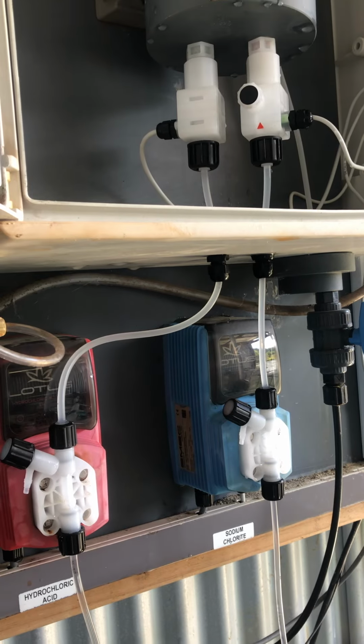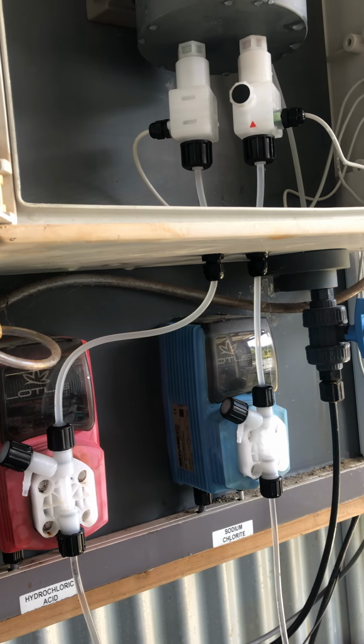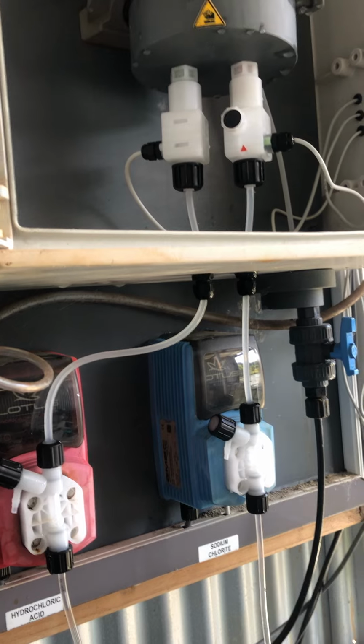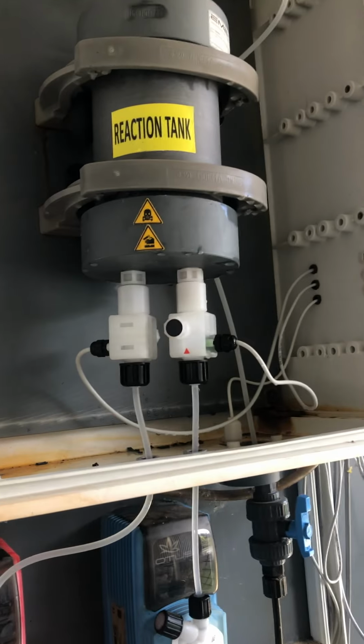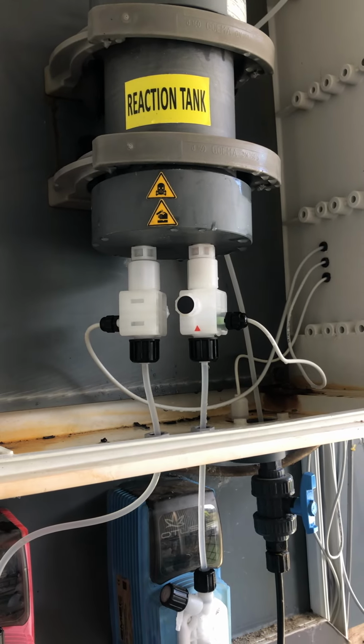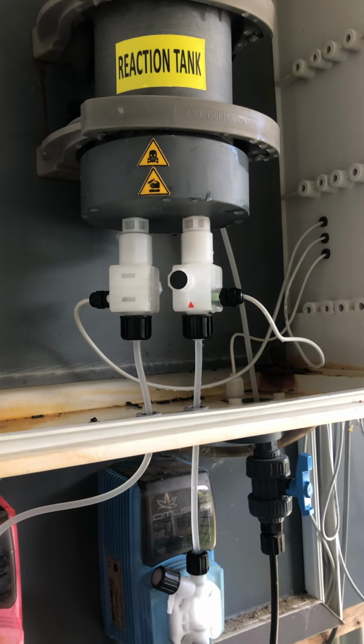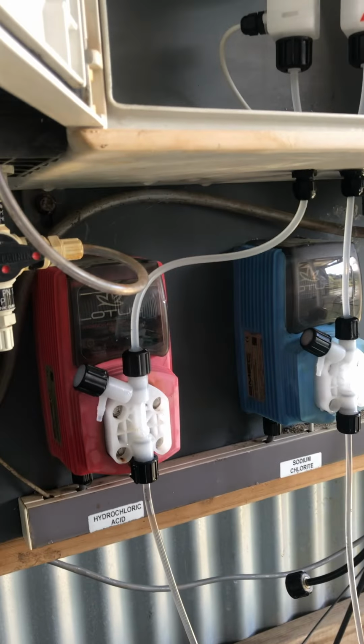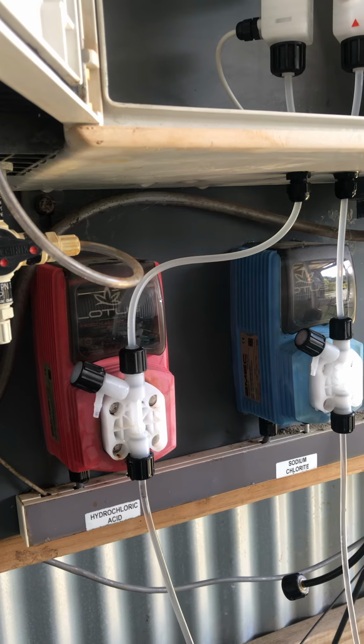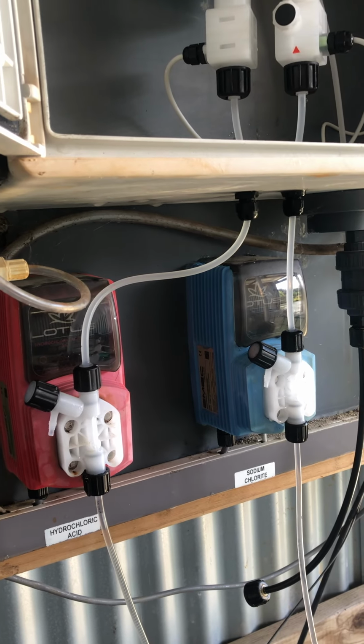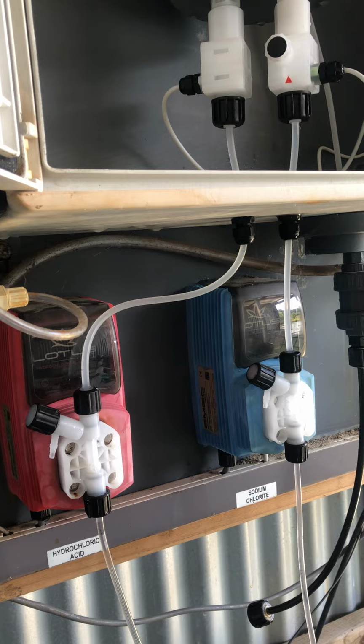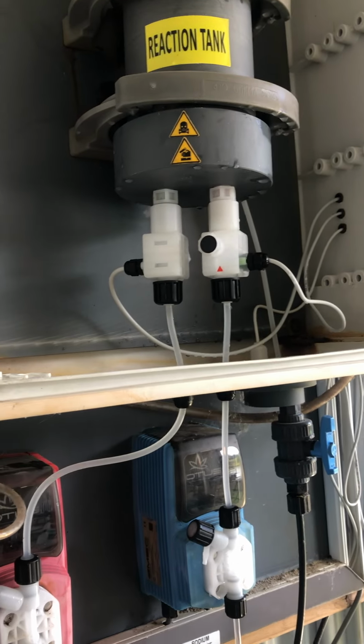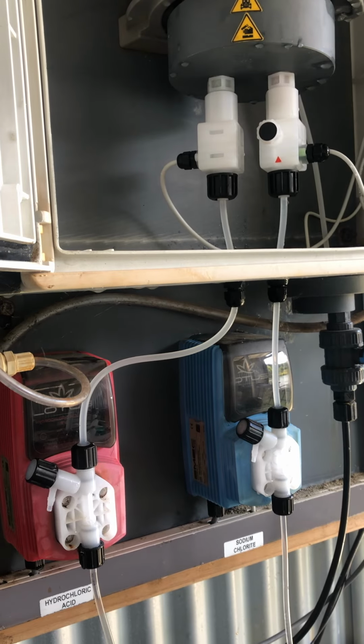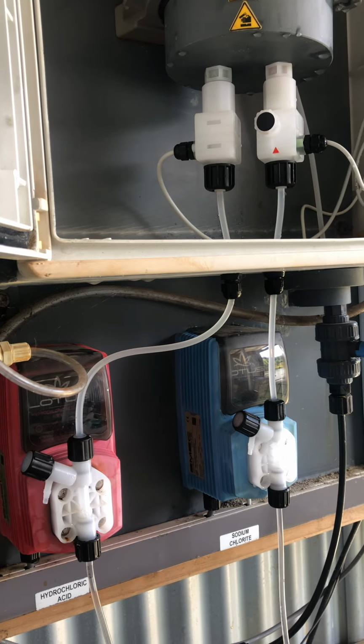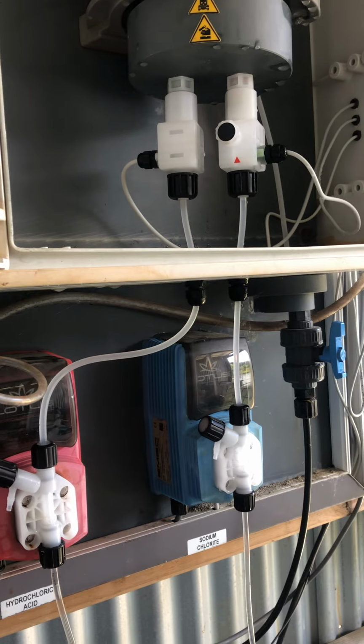We then replace the PVDF tubing. I recommend that you don't cut that initially. Disconnect it from the half-inch fittings in the bottom of the flow monitors and disconnect the 3/8 fitting on the top of the valve. Remove the tubing connectors where you can, then slide the tubing out and measure each length to the same length of the PVDF tube to make it a lot easier to refit it.